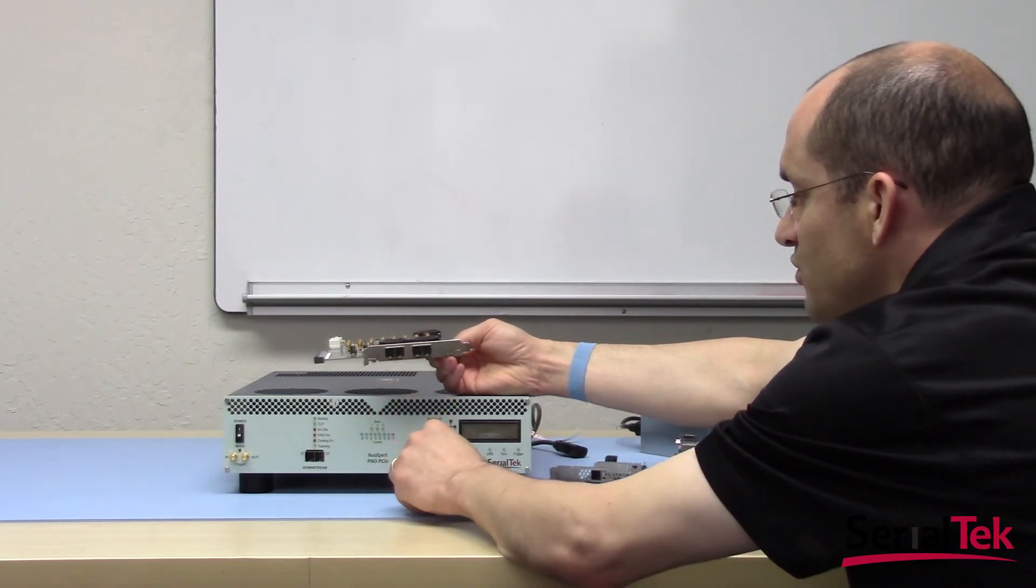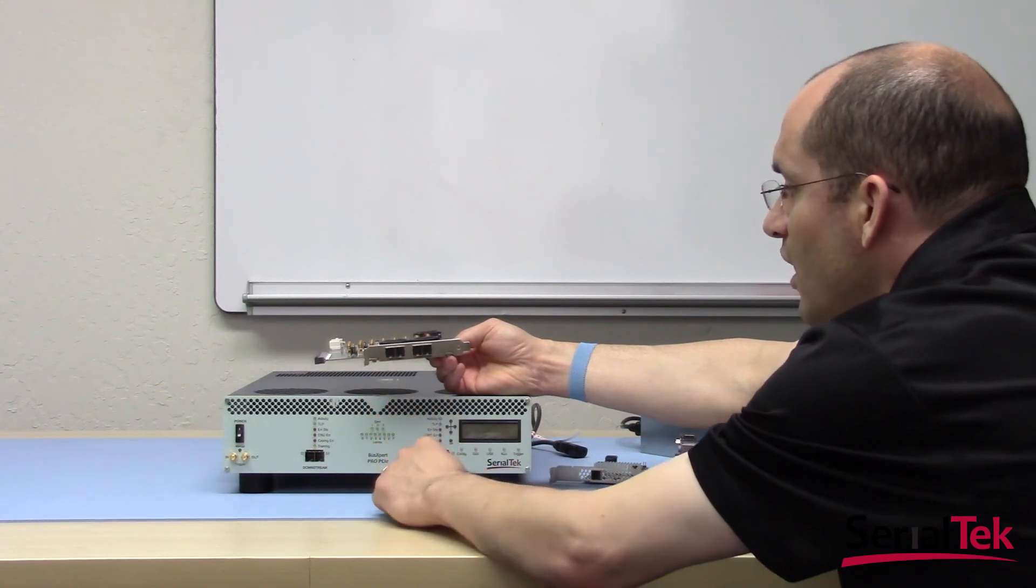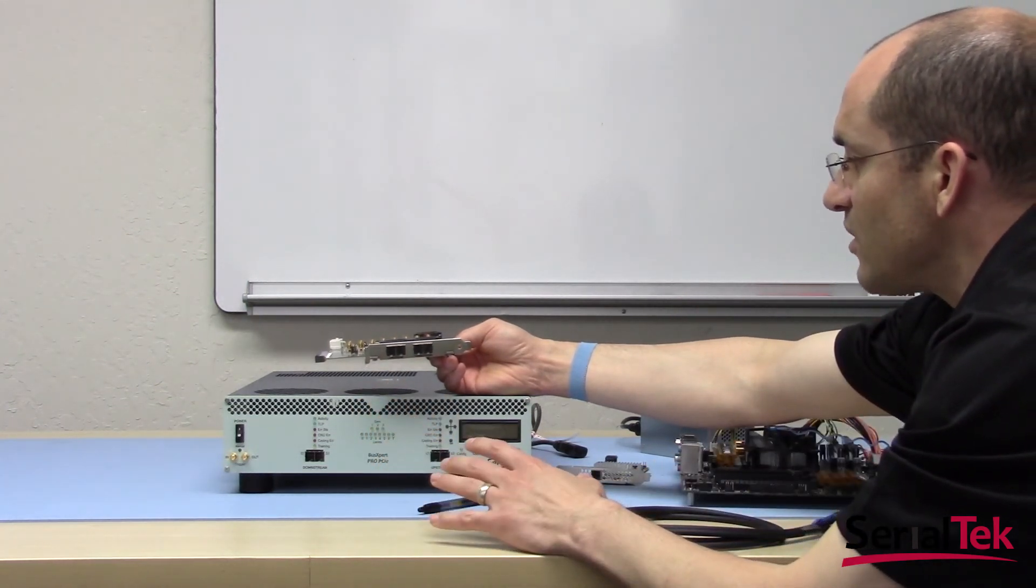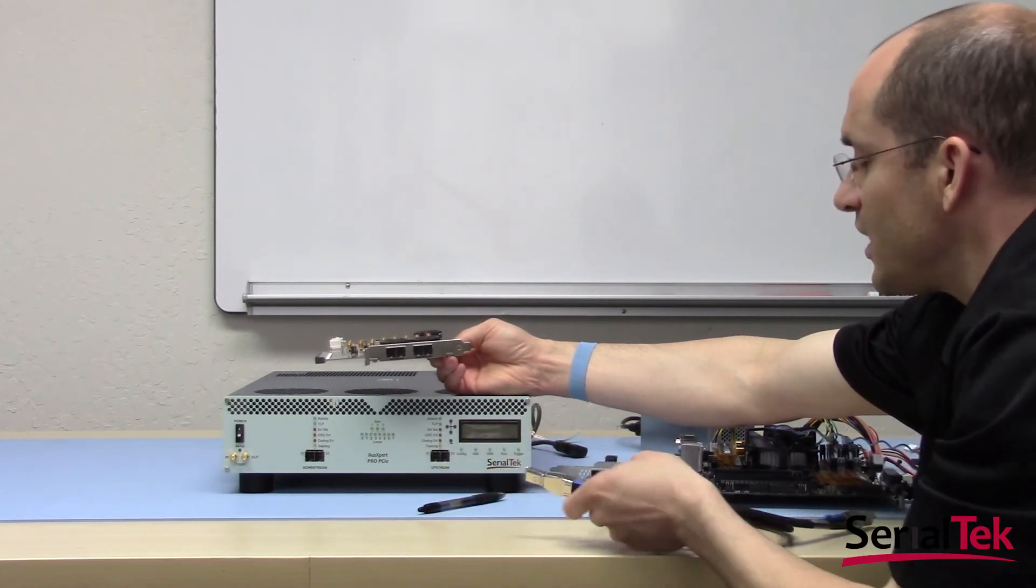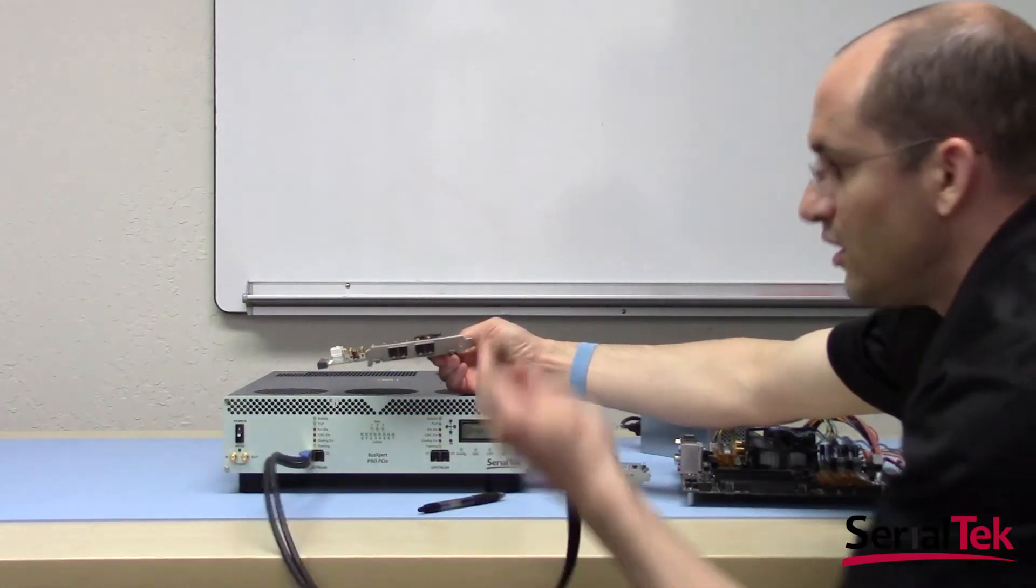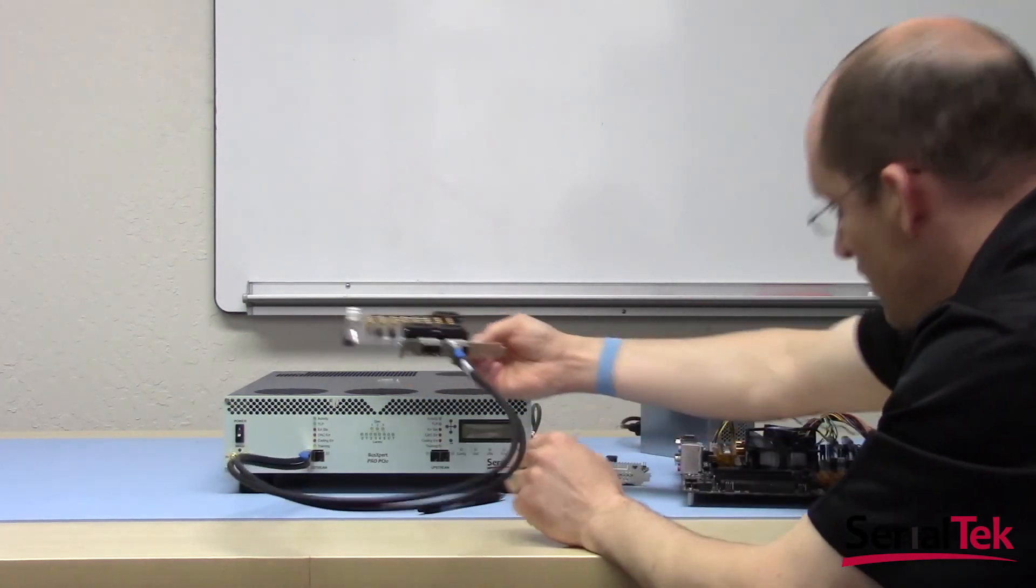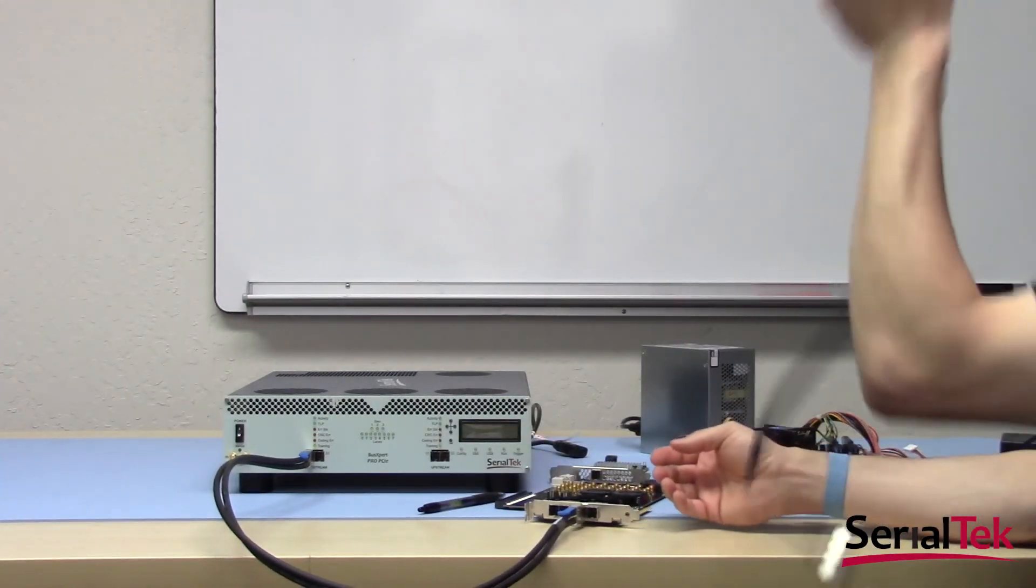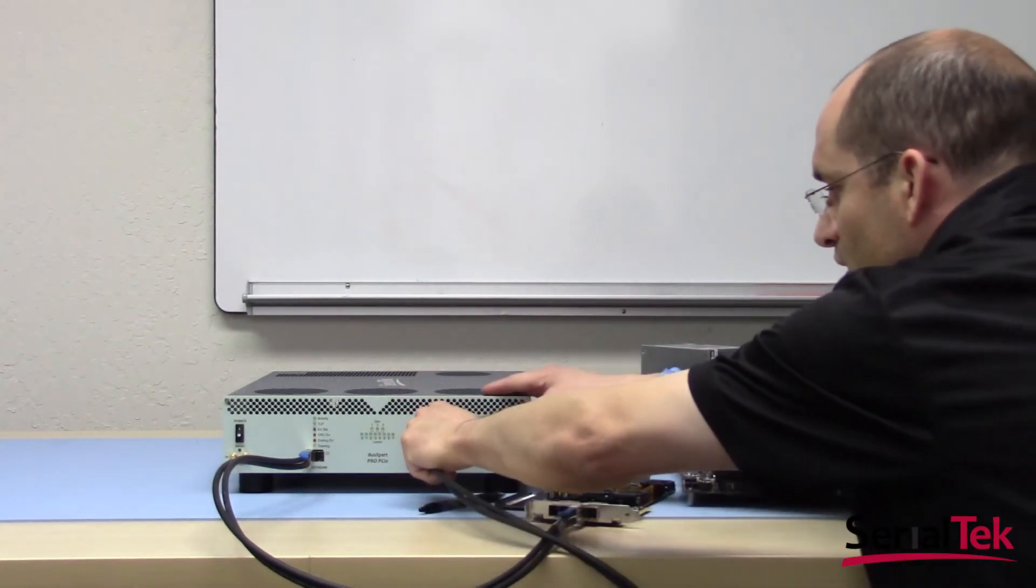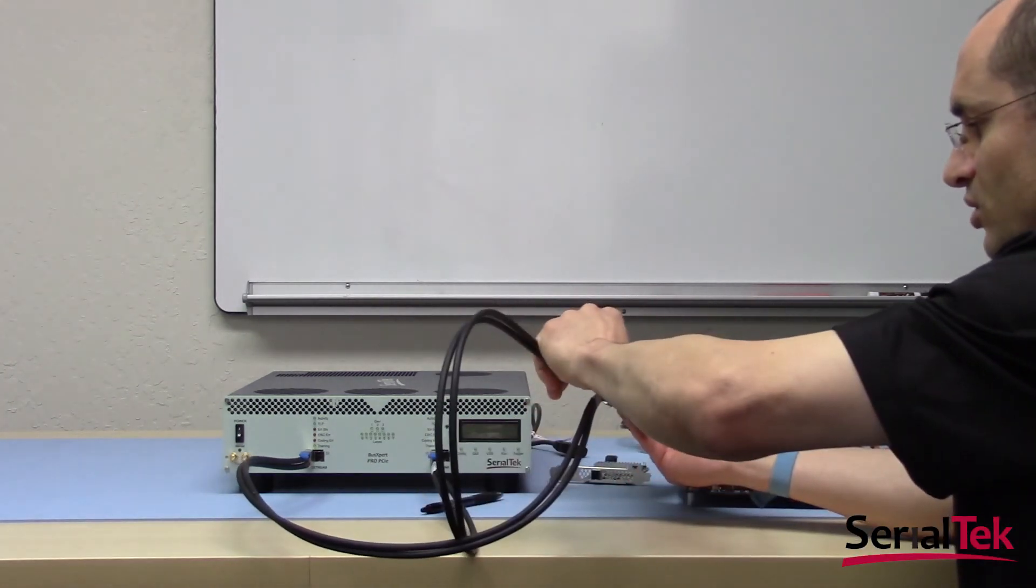For upstream, U1, the leftmost connector on the upstream port, to U1 on the interposer. And so as long as that's kept straight, again, the connection connecting the analyzer and the interposer is very straightforward. So we'll go ahead and do that now. Again, connecting D1 on the analyzer to D1 on the interposer. And then with the second cable connecting U1 on the analyzer to U1 on the interposer.